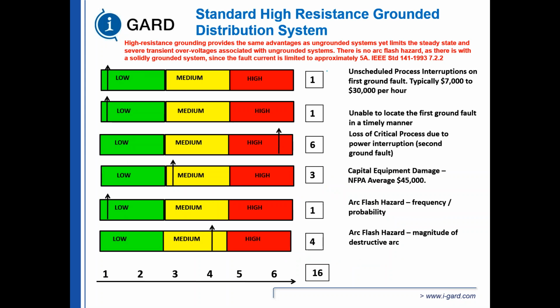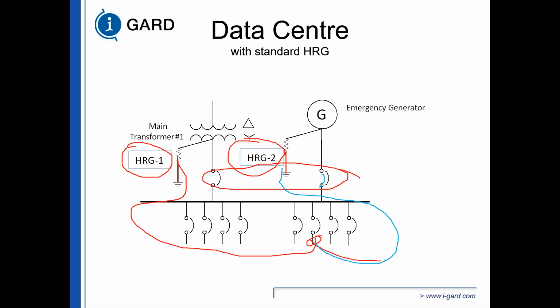So because you have high resistance grounding with a standard HRG system, your unscheduled process shutdown is going to be low. Your ability to locate the first fault is going to be high because you have pulsing and you can find where the fault is. Loss of critical process due to the second fault: if you have a second fault that occurs on a different phase, and let's assume we have a different feeder, something is going to shut down.